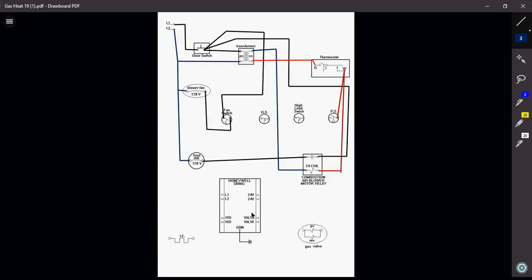Okay? So, once my thermostat closes, I am now going to send 24 volts down to this coil, which is now going to close those contacts, which is now going to make my vent motor, inducer motor, start to spin. Once it starts to spin, and I sense my pressure difference inside my heat exchanger, and it's telling me that everything is good to go, that pressure switch is now going to close.